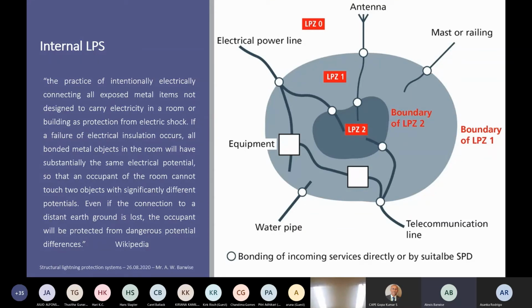And if there's anything you would ever remember about the internal lightning protection system, it's exactly this. It doesn't matter about the earthing necessarily. It doesn't matter about how the lightning protection system functions on the outside. Internally, if we ensure that all metals which I can touch as a human being, so the standard speaks of within an arm's reach, are connected together intentionally, we are avoiding a shock or an electrocution because we have ensured that the potentials are at the same value.